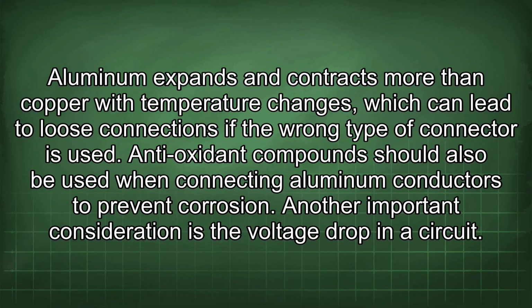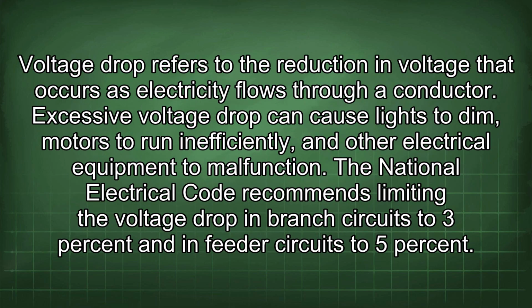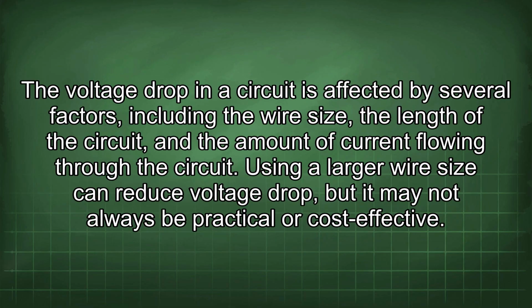Another important consideration is the voltage drop in a circuit. Voltage drop refers to the reduction in voltage that occurs as electricity flows through a conductor. Excessive voltage drop can cause lights to dim, motors to run inefficiently, and other electrical equipment to malfunction. The National Electrical Code recommends limiting the voltage drop in branch circuits to 3% and in feeder circuits to 5%. The voltage drop in a circuit is affected by several factors, including the wire size, the length of the circuit, and the amount of current flowing through the circuit.